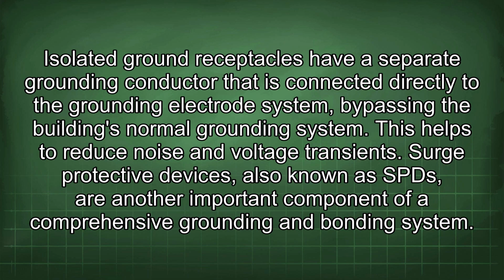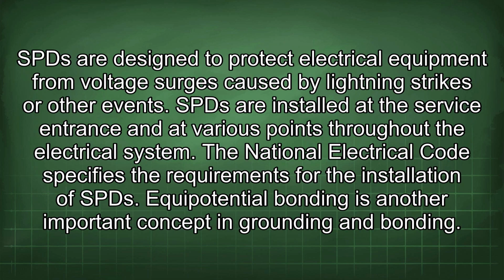Surge protective devices, also known as SPD, are another important component of a comprehensive grounding and bonding system. SPD are designed to protect electrical equipment from voltage surges caused by lightning strikes or other events. SPD are installed at the service entrance and at various points throughout the electrical system. The National Electrical Code specifies the requirements for the installation of SPD.